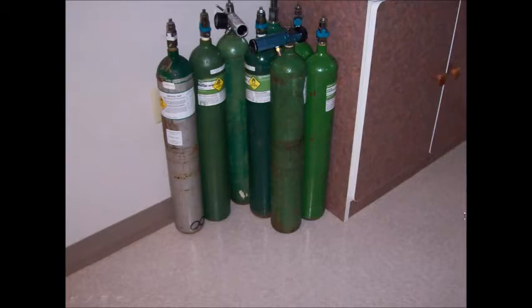How about oxygen? Low-hanging fruit, and I've already gone through a lot of them. Wedge doors, sprinkler heads that are compromised, storage height that's too high, or oxygen cylinders that are not properly secured within your facility. I took this picture at a facility in Louisiana about a year after Hurricane Katrina. The good guys from around the country came in to rescue, to provide assistance, and they left some of their equipment behind. And when I went and visited a facility to do a survey to make sure that they were back up and running in a safe manner, I found a room where those oxygen cylinders were just in a corner.